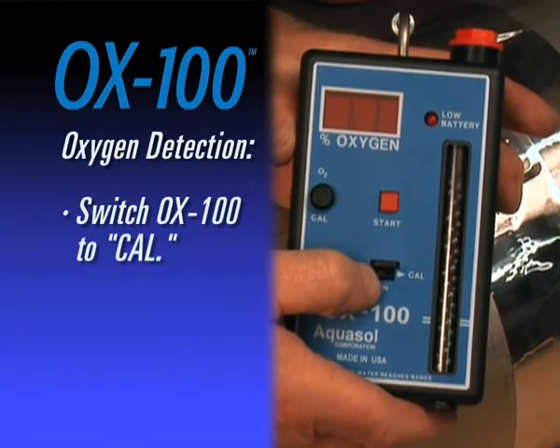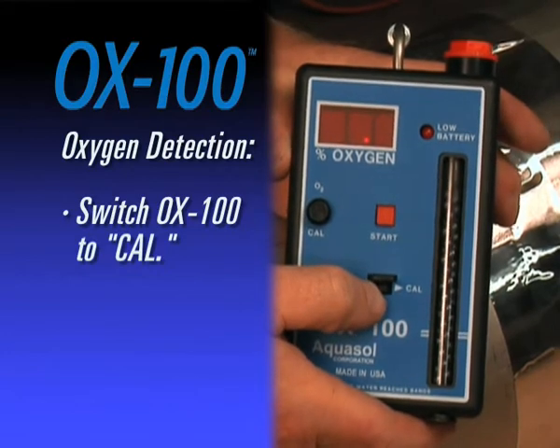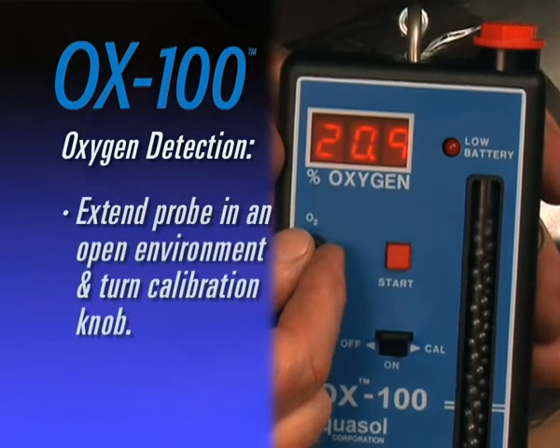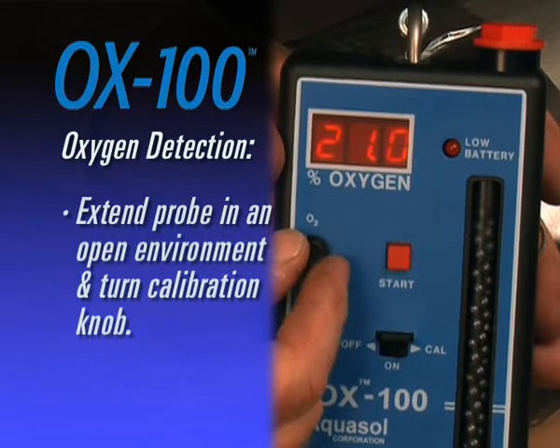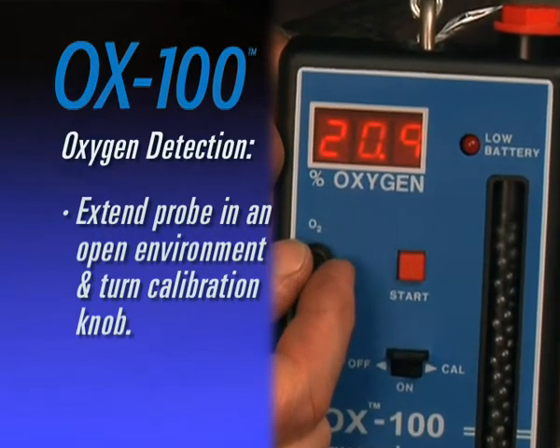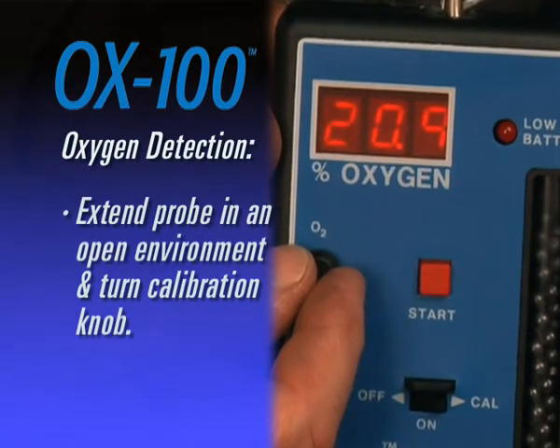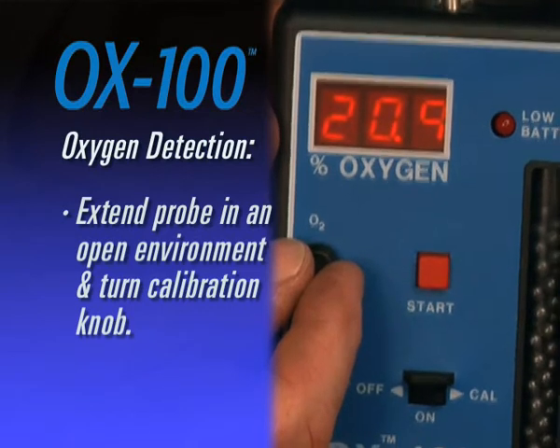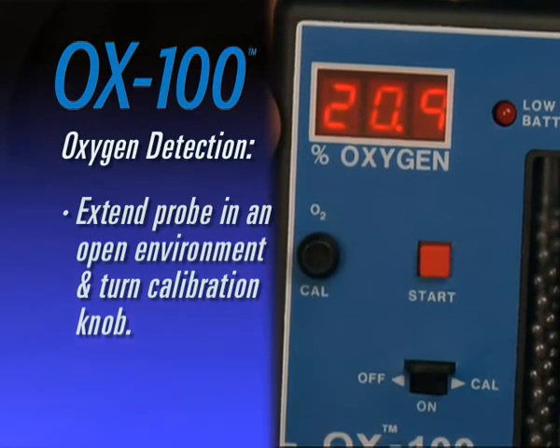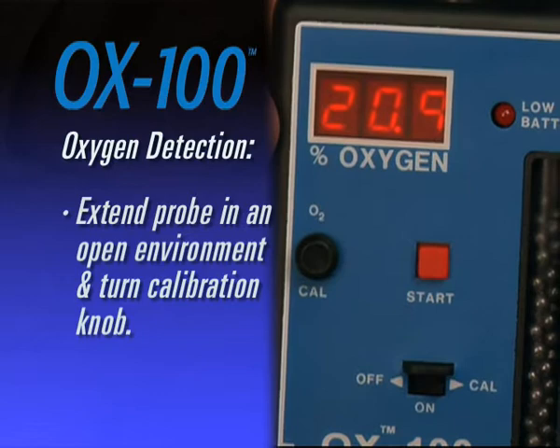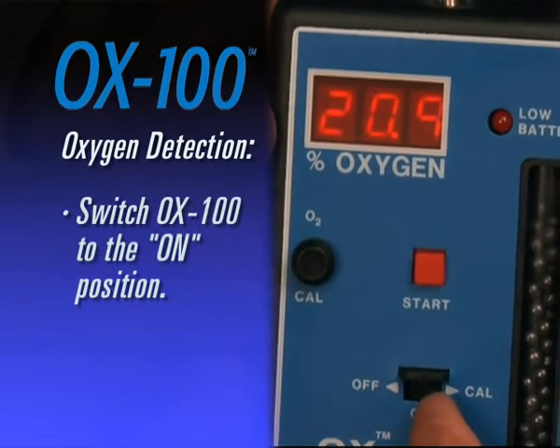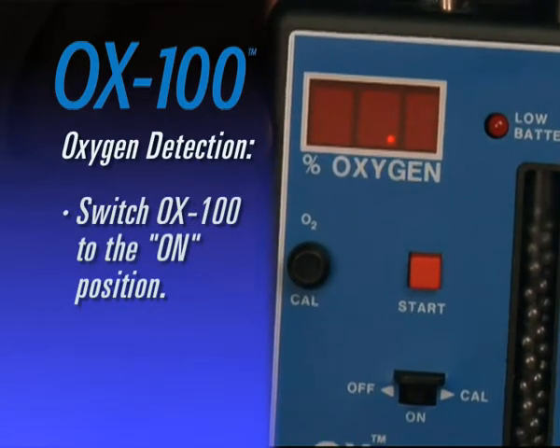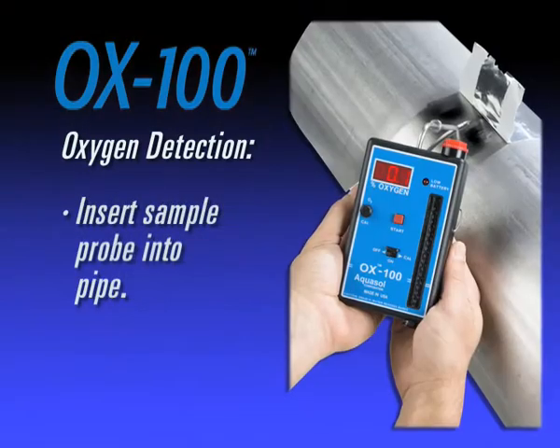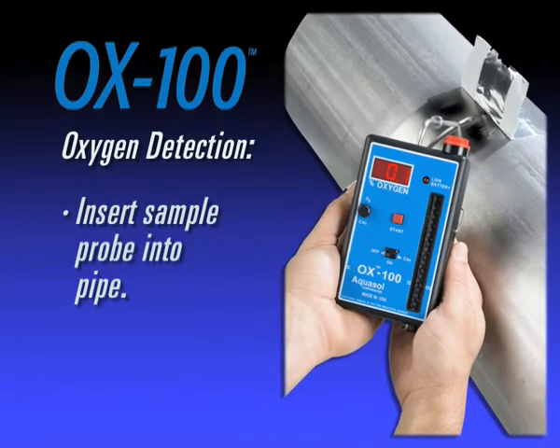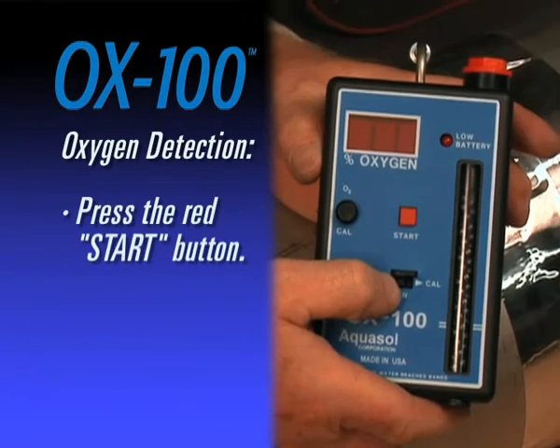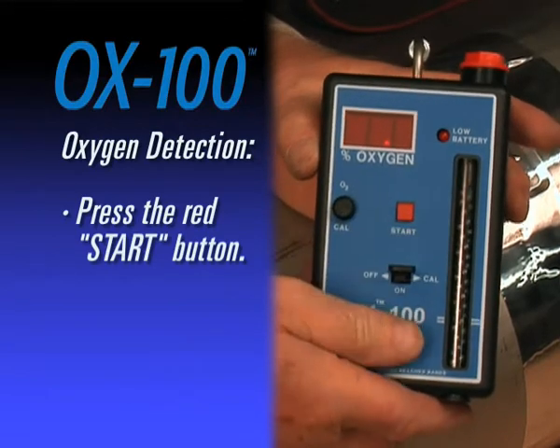First, switch the OX-100 to the Cal position. Next, extend the sample probe in an open environment and turn the calibration knob to the left or right. The reading will appear within 30 to 60 seconds on the digital display panel, displaying 20.9%. Switch the OX-100 to the On position. Insert the sample probe into the pipe or desired location and press the red Start button once to begin the reading.